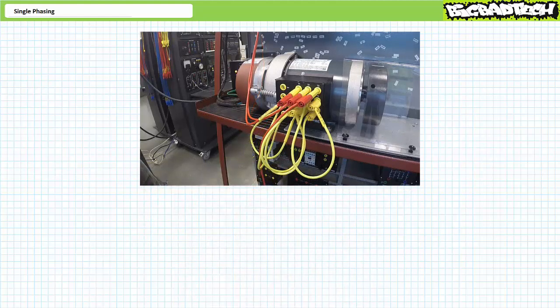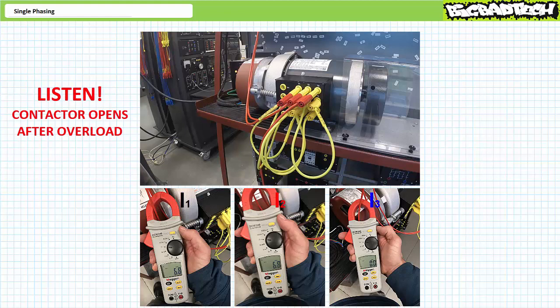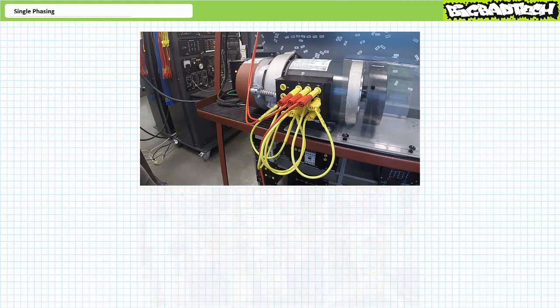Let's now try to single phase this motor from a stop state. Do not try this at home. When energized with only phase L1 and L2, the motor experiences a surge of inrush current in the remaining phases and fails to initiate rotation. Current in the lost phase is non-existent and current in the remaining phases is a substantial 6.8 amps. Additionally, the motor buzzes like a hive of angry bees. Given the overload element presently set at 1.6 amps, it quickly signals an overload and the motor starter breaks connection by opening the contacts.